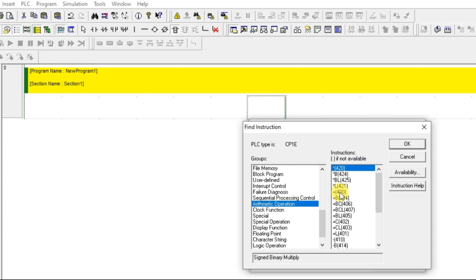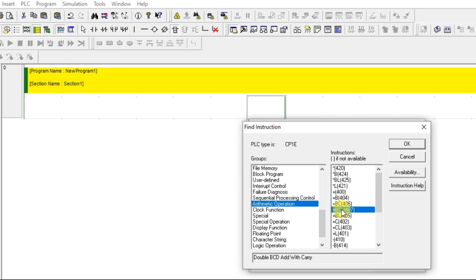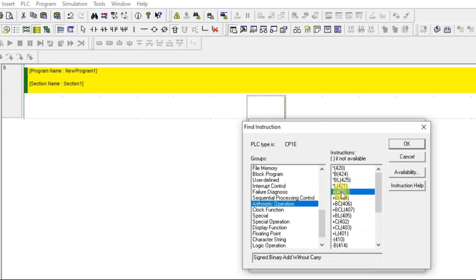Let us look at the PLUS instruction. You can see there are several PLUS variants. The basic one, PLUS 400, is a signed binary add without carry. There is also a BCD add with and without carry, and a double integer version for 32-bit addition. So Omron PLC gives you multiple options, but we will use the basic one.